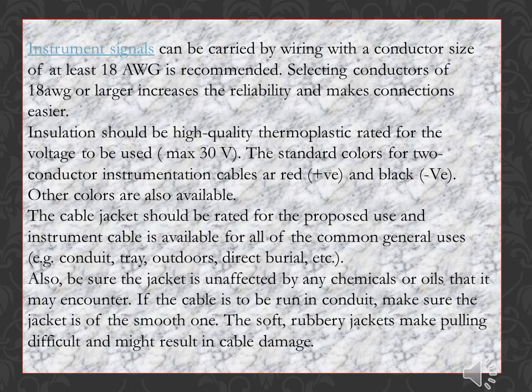The cable jacket should be rated for the proposed use. Instrument cable is available for all common general uses such as conduit, tray, outdoors, and direct burial. Ensure the jacket is unaffected by any chemicals or oils it may encounter. If the cable is to be run in conduit, make sure the jacket is smooth, as soft rubbery jackets make pulling difficult and might result in cable damage.